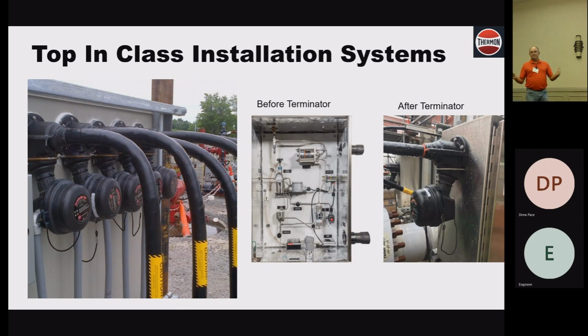It expands. What's happening to that heater cable if it's expanding? Where's it going? The way we build it, we wrap that cable around it, so it will twist with the bundle as it stretches and won't damage it. I've seen bundles pulled in half before. We had one in Georgia where they installed it and tied off the end. It was 375 feet long, and it stretched the outer jacket that far, pulling wires apart inside the bundle. I was able to fix it, but we couldn't guarantee it would last. That's the problem, but anyway, installation is the number one cause. If it's done right, it'll last for years, and y'all know that.